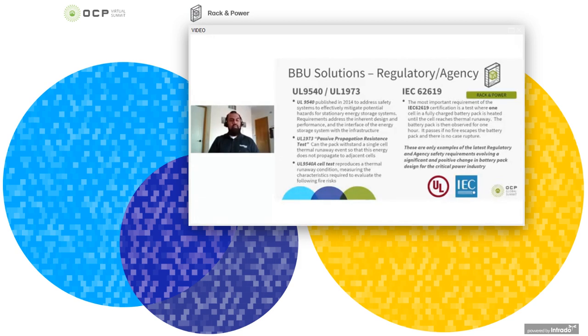One common test that is new from previous standards is this thermal runaway test. The test procedure calls out that one of the lithium ion cells be artificially put into thermal runaway. The test tries to ensure that the complete pack doesn't go into a thermal runaway and fire doesn't escape the case. Again, this is to ensure if a lithium ion cell fails, it fails safe and it doesn't take out the whole battery.